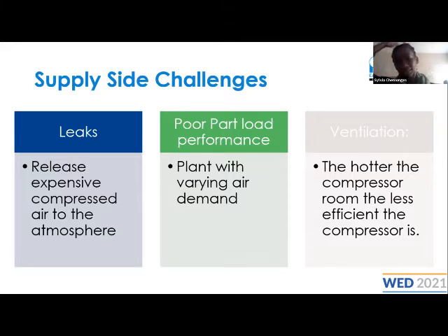At most sites, you'll see the compressor room is very small and the compressor is crammed up in a small space somewhere. So these compressors do not have adequate flow of air, and the environment ends up overheating. The compressed air generation in such an environment that has high temperature tends to be very inefficient.